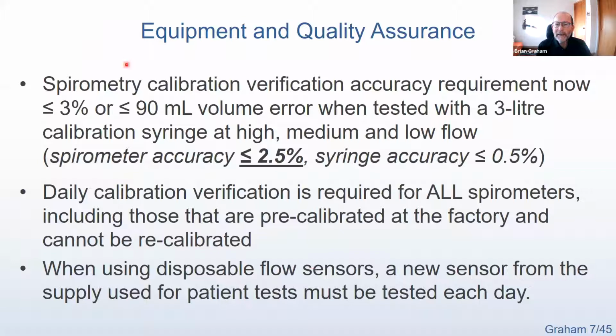In terms of the equipment, the first big change was spirometry accuracy, and we specified 2.5%. The calibration syringe accuracy remains at 0.5%, so the combination of the two of them gives a plus or minus 3% accuracy requirement. When we contacted manufacturers and looked at their websites and so on, we found that in most cases, the accuracy specified was 2%.